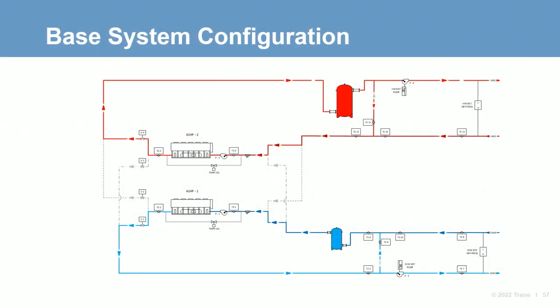As Charlie introduced earlier, four-pipe distribution, dual feed, is the base configuration recommended for use with multiple air-to-water heat pumps. Note that this system applies to packaged or modular units. While other system configurations are possible and will not be unusual, this one provides excellent flexibility and simplicity of design and control. Let's dig into the system. We know the system is a primary-secondary configuration, but how does the plant work?